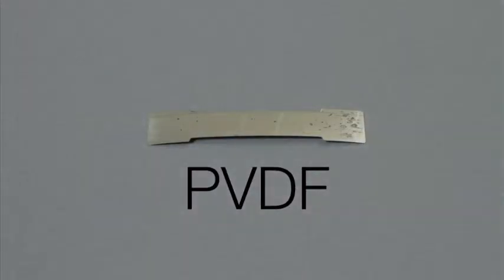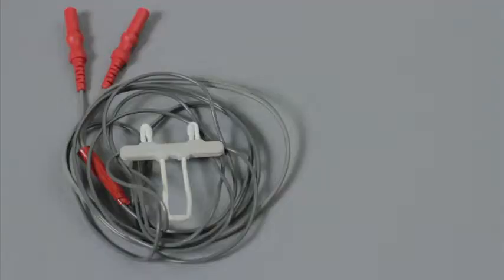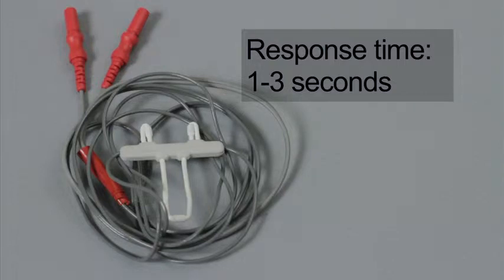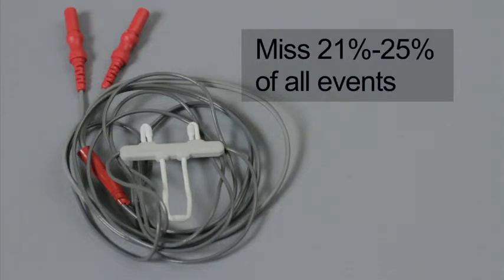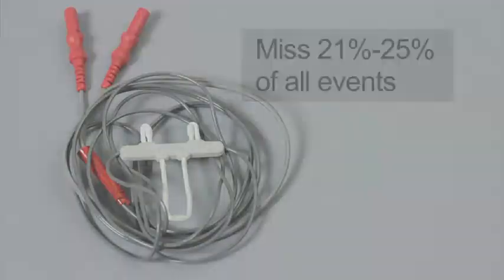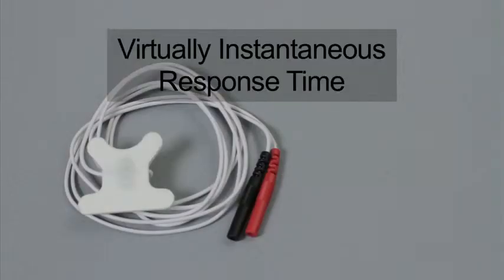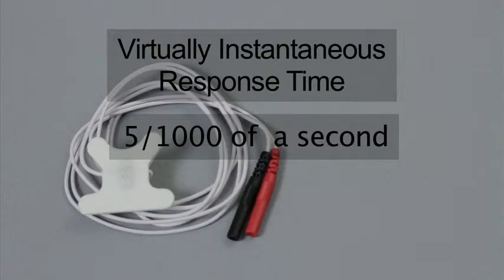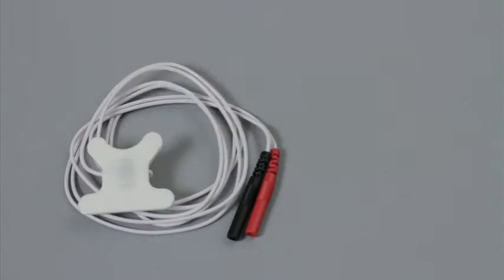The biggest advantage of using PVDF as an airflow sensor is in its response time. Traditional sensors like thermistors and thermocouples measure airflow by changes in temperature, but the response times can be as much as 1 to 3 seconds. Consequently, the data must be averaged to produce a waveform on a polysomnograph. One study said that therms miss anywhere from 21 to 25% of all events. PVDF has a virtually instantaneous response time of 5/1000ths of a second. It does not have to average the data and is therefore a better event detector than traditional thermal sensors. It will not miss events.